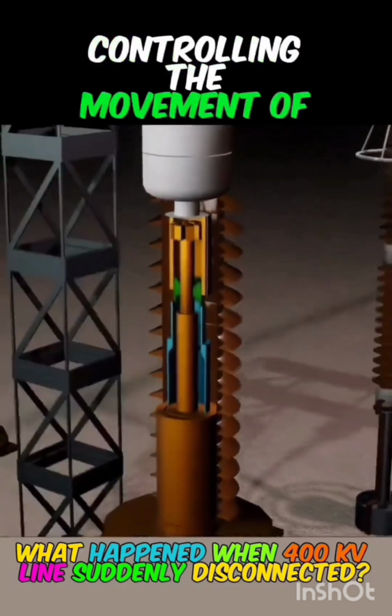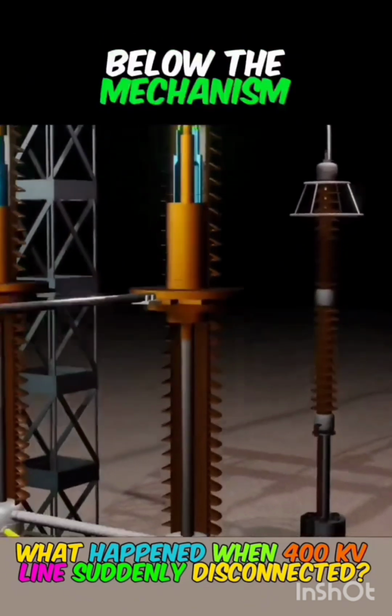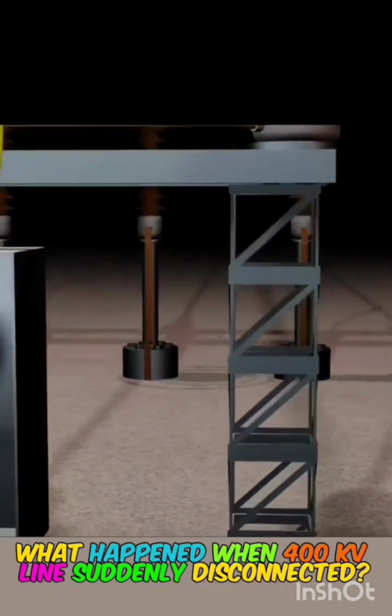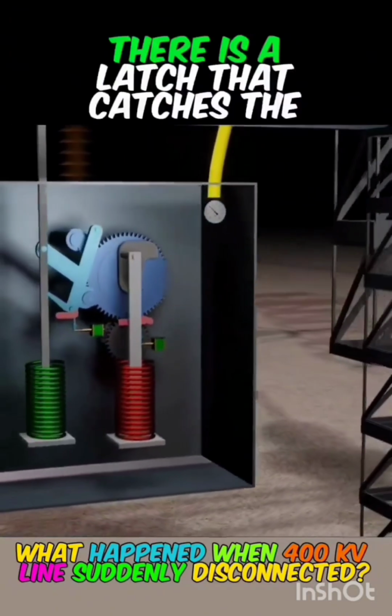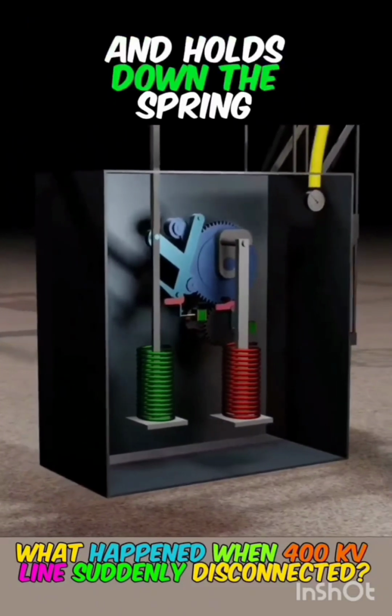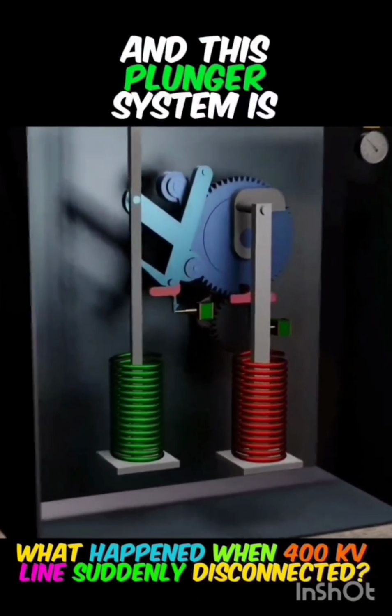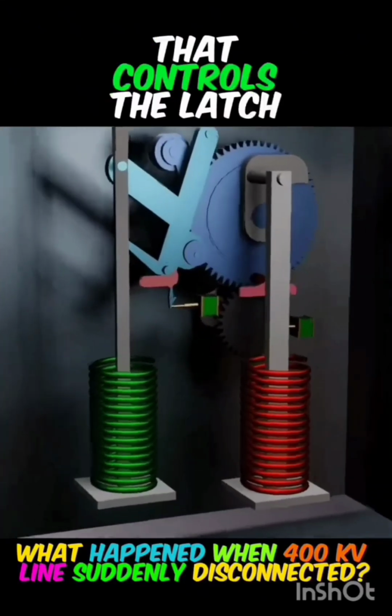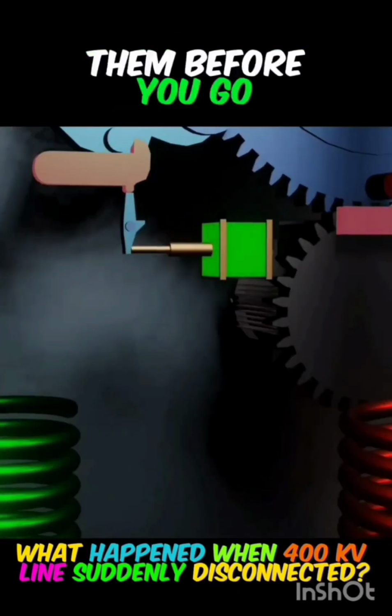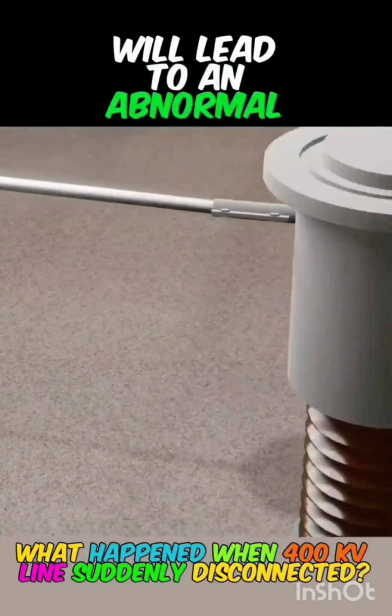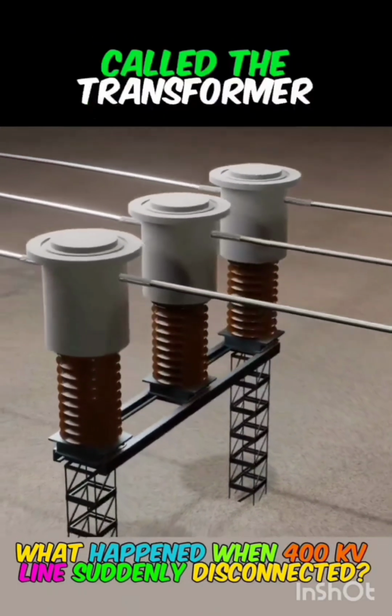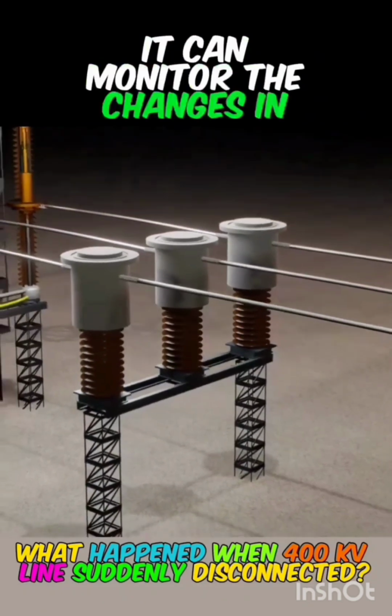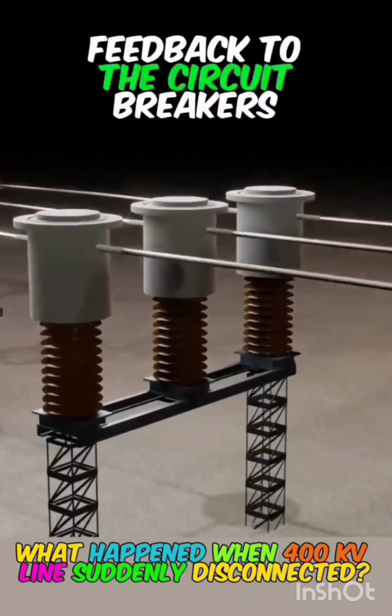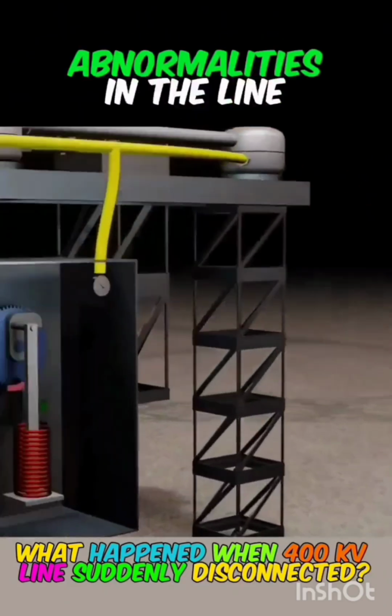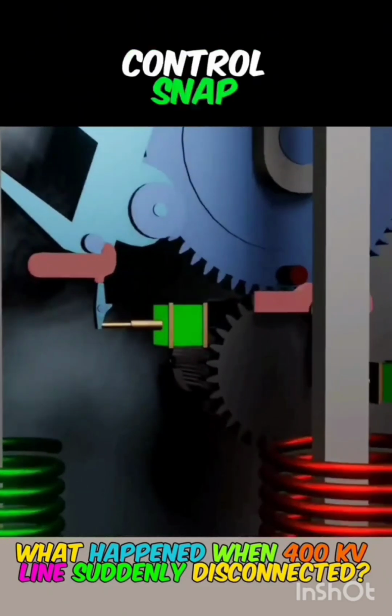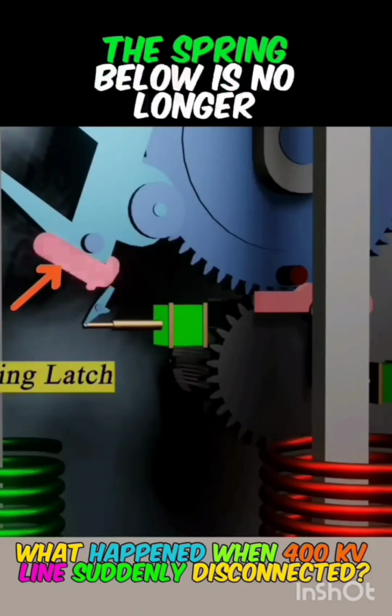Controlling the movement of the sleeve is the circuit breaker mechanism below, which has two springs inside. When the line is connected, in the state of force, there is a latch that catches the lever and holds down the spring that stores the force underneath, and this plunger system is connected to a relay that controls the latch. When there is a fault in the line, it will lead to an abnormal increase in current. Next to these components is the transformer, which can monitor the changes in current. It will feed the anomalies back to the circuit breaker's relay, telling it that there are abnormalities in the line and it should be tripped.